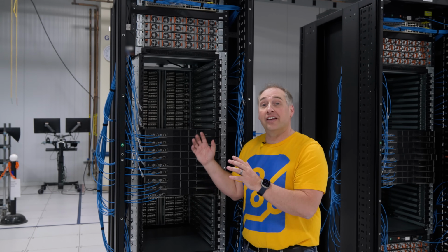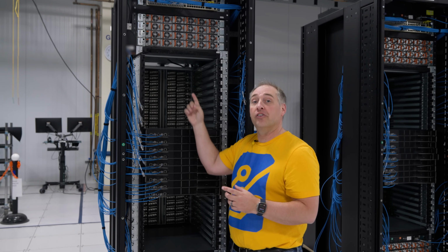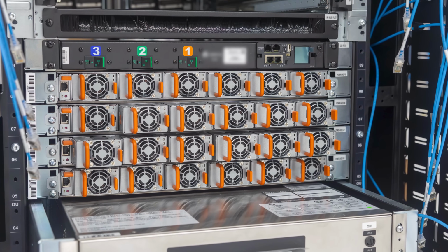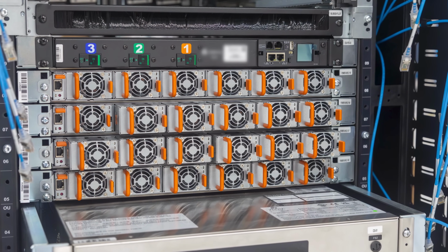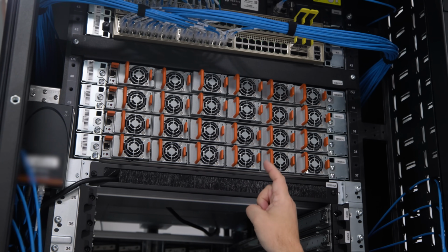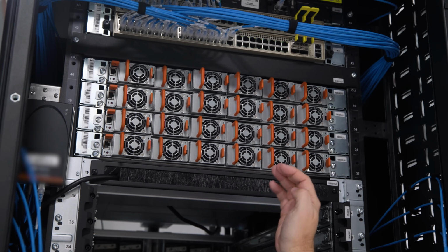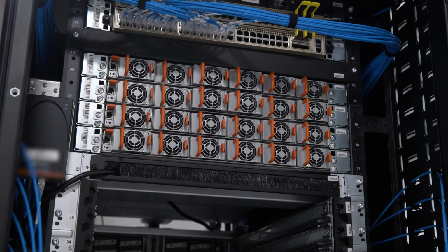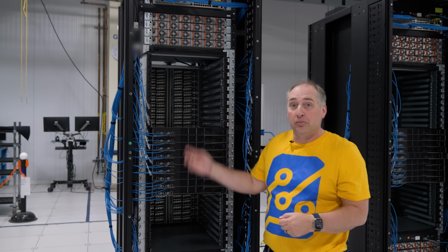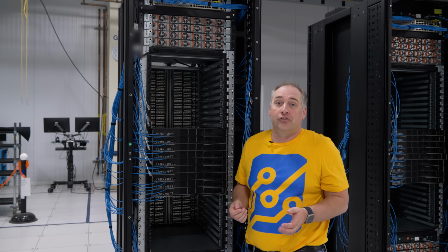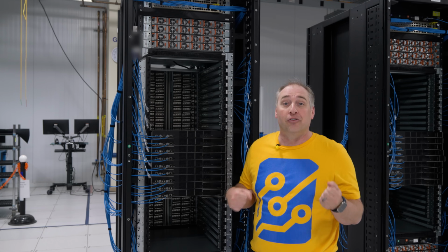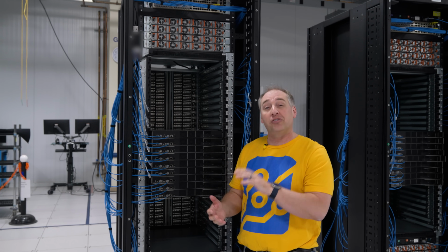And so the way everything is powered is that these power shelves that are up here and also down below, these are really designed to provide all of the power that all of the components need, so you don't need those individual power supplies. And especially, you don't have to go and cable all of those. Imagine going and cabling two power supplies per node versus just doing a couple of large cables in the rear. It's much easier to manage, especially at this scale.